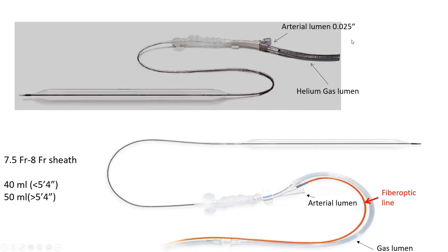Now, this lumen is used to monitor the arterial waveform. The problem is that it's such a small lumen that it commonly clots. Then you're not able to monitor the arterial waveform. Then you end up having to replace the balloon pump or use the suboptimal radial line connected to the balloon pump console and monitor the arterial waveform. That's why modern balloon pump has actually a third lumen, which is the fiber optic line, which is connected to the tip as well, and which allows monitoring of the aortic waveform using fiber optic plethysmography technology.